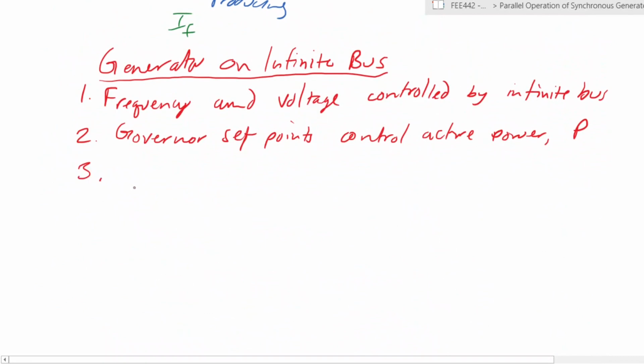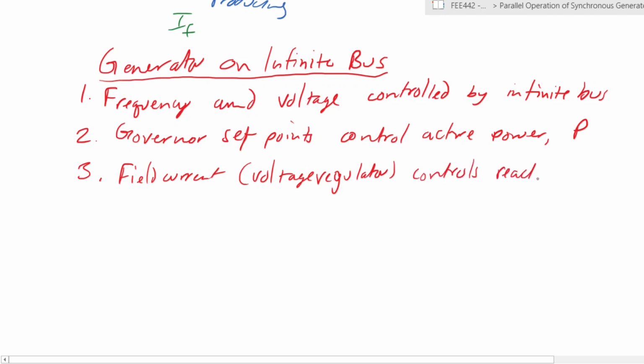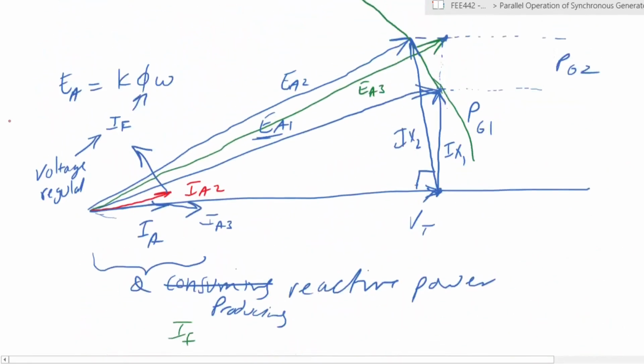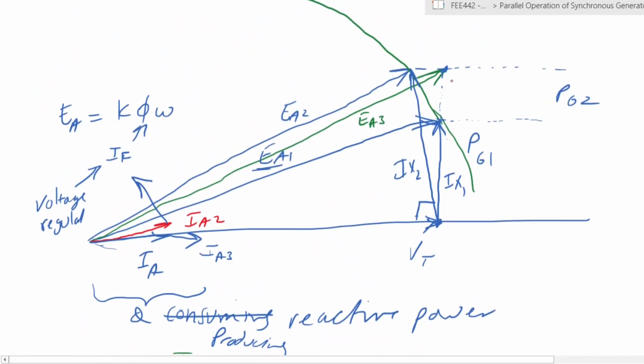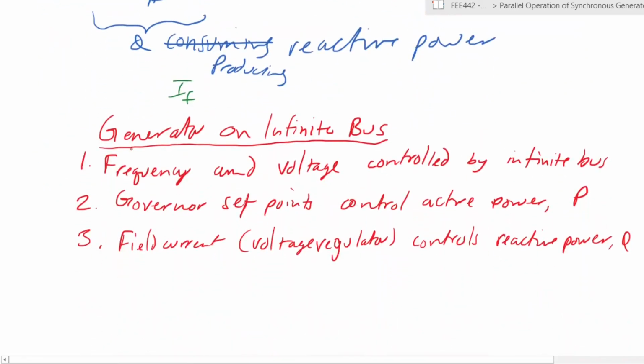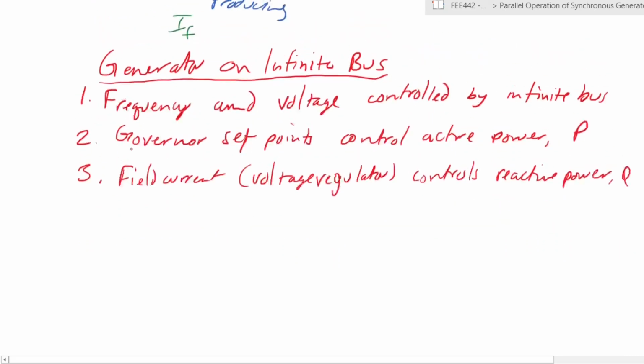And then number three, the field current, or voltage regulator, controls reactive power. And we saw that over here, whereby in order for us to change the power factor at which the machine is operating, we changed the current, which changed the value of flux. These things are all related to each other.